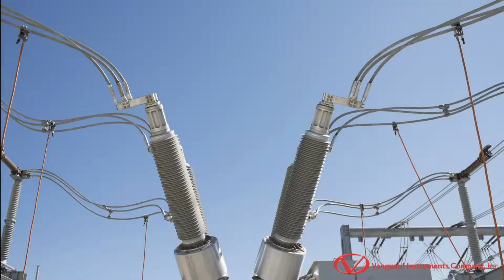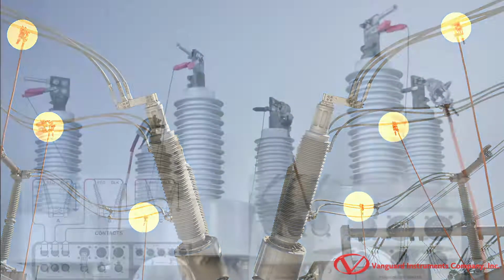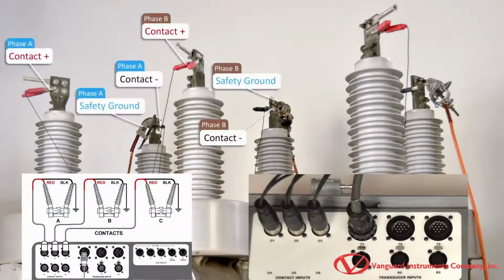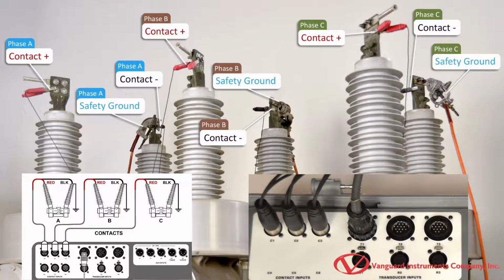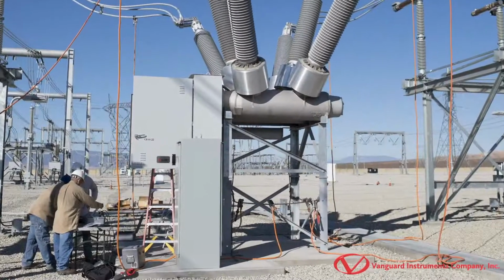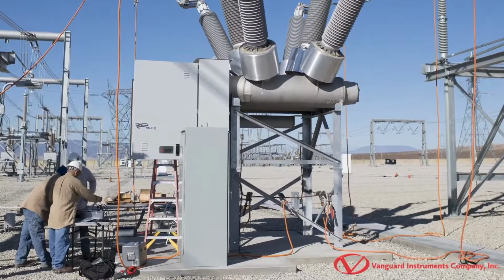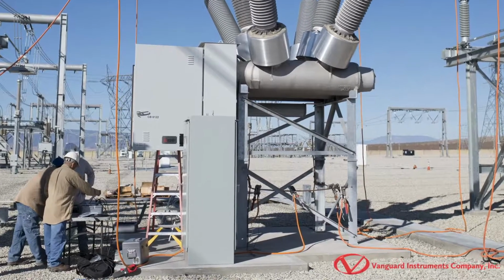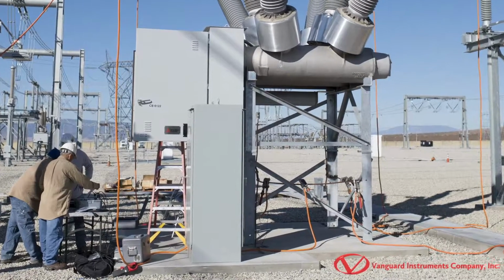With this traditional method of testing, both sides of the circuit breaker are grounded while test connections are being made, but only one side of the breaker can be grounded during testing. This creates a major safety hazard as the breaker may be energized by induction from nearby circuits. However, these risks can now be virtually eliminated by a novel test technique that allows both sides of the breaker to remain grounded while testing.